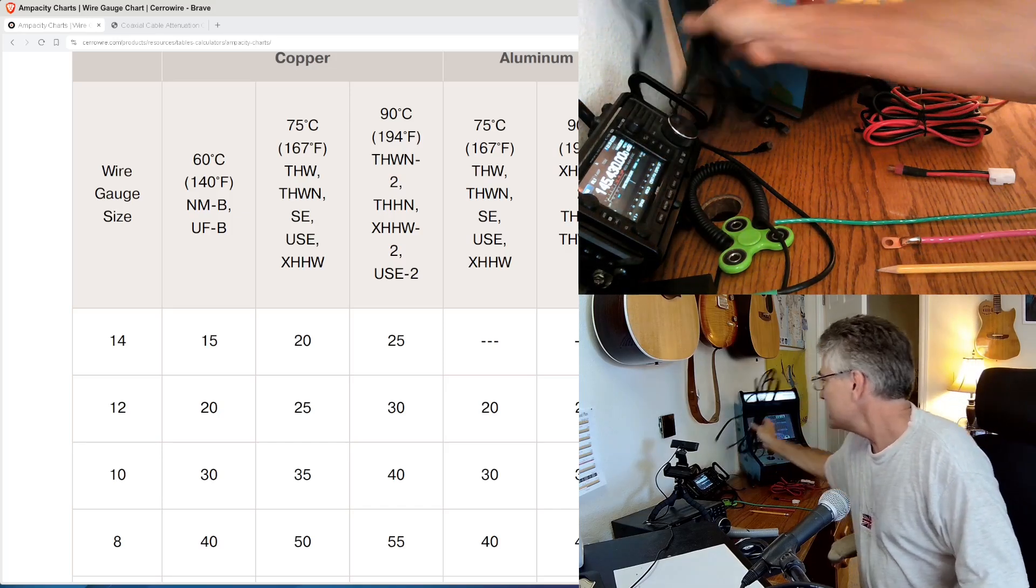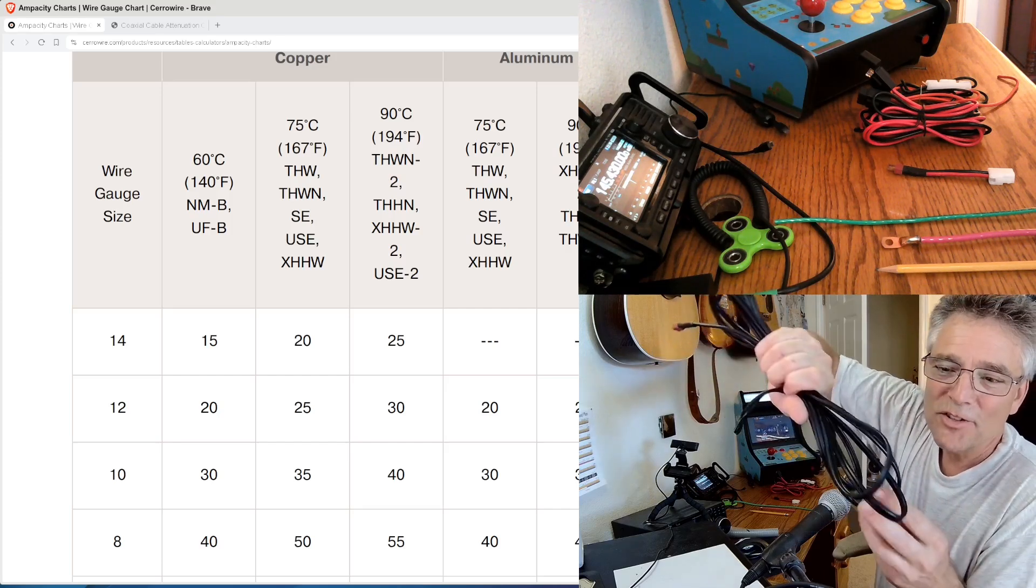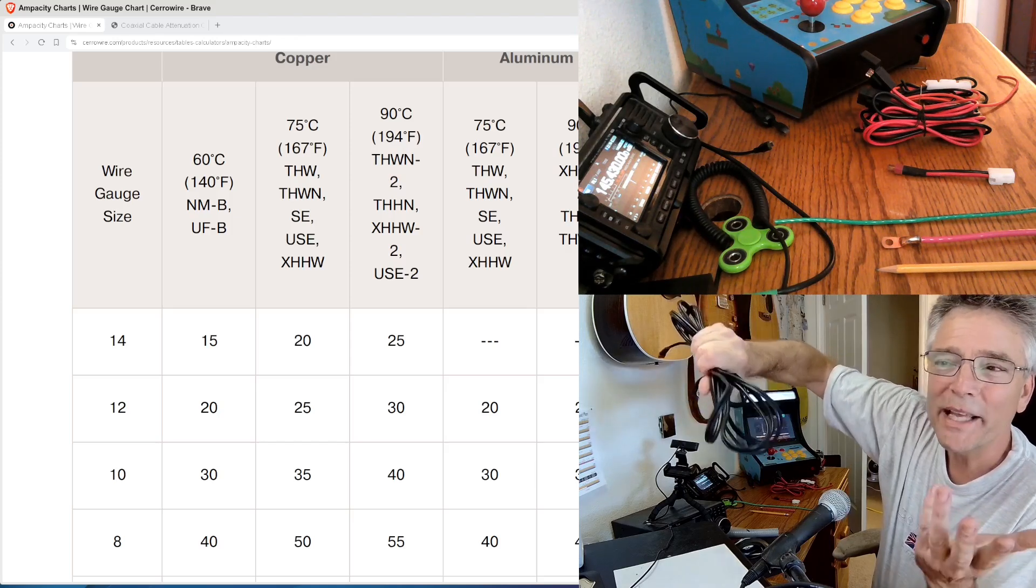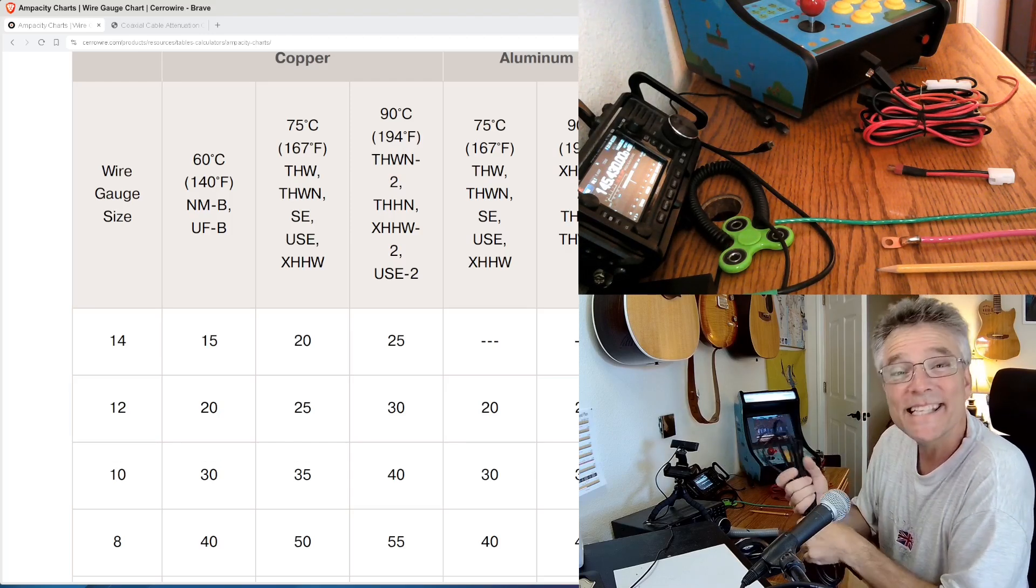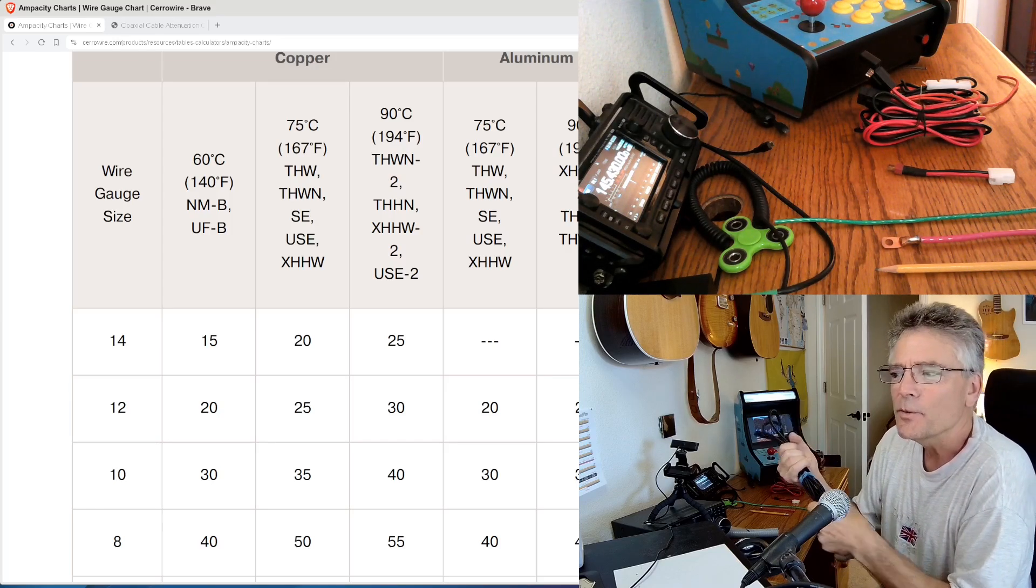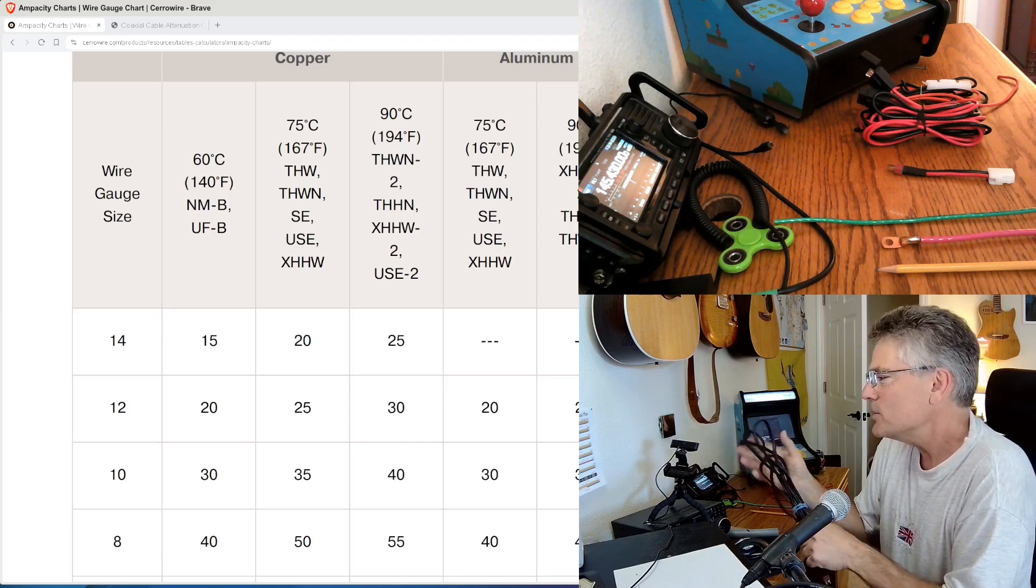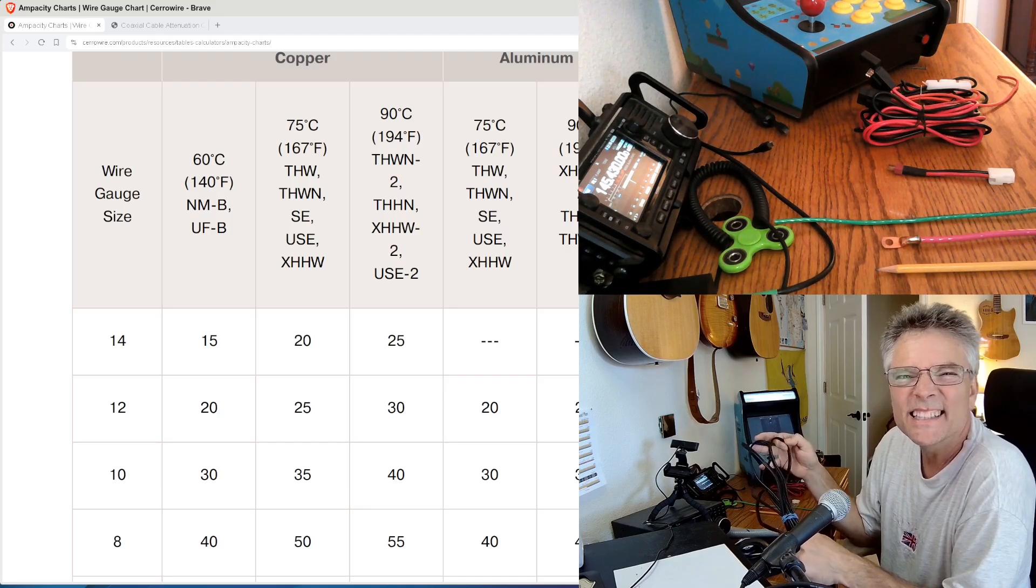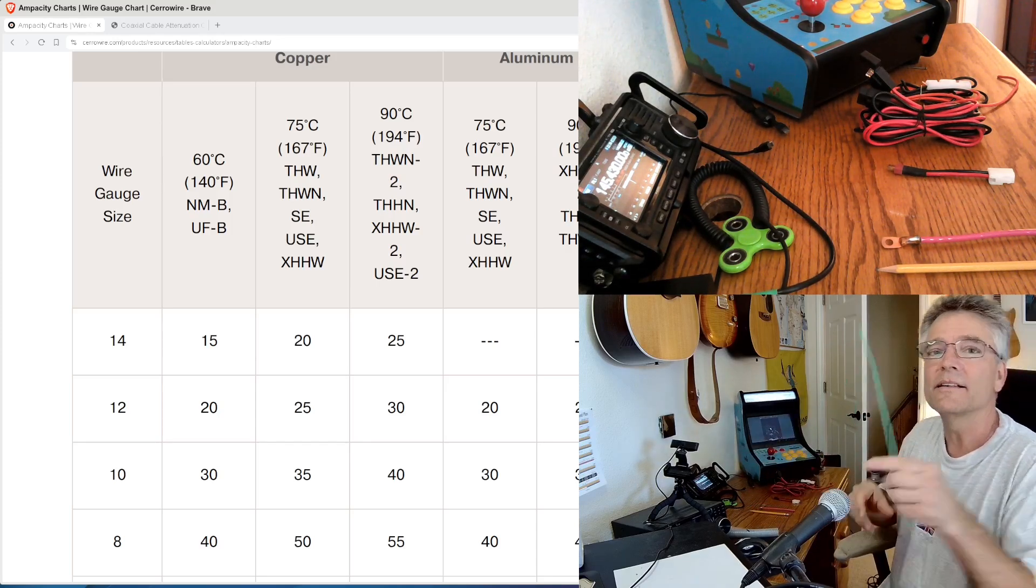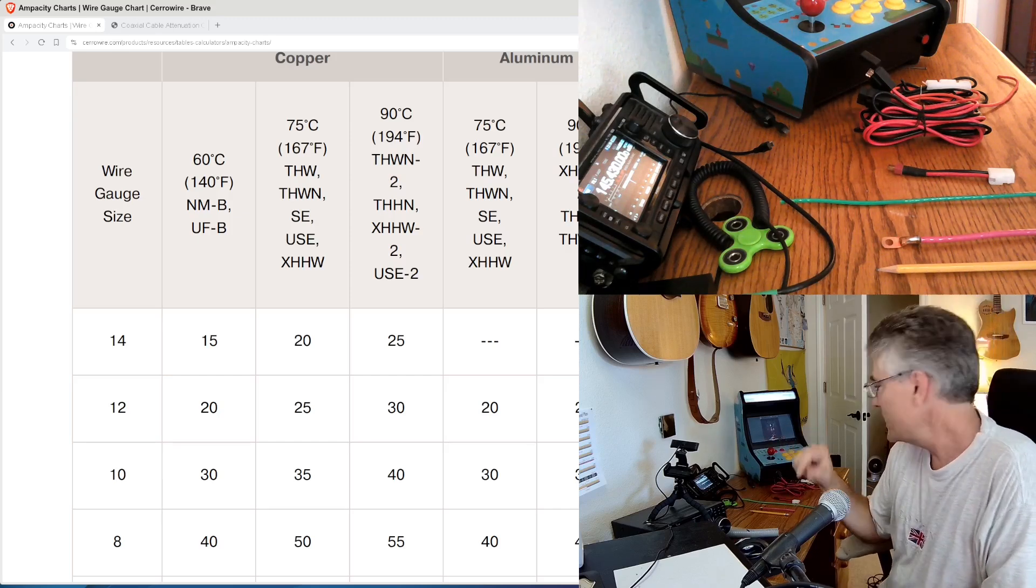If you need to do some longer runs, wire is expensive, let's face it. I actually go to the garden store and get some of this. This is 12-gauge wire and it is direct burial grade, and 12-gauge will carry maybe 20 amps. Now this is not UL listed, so do not put this in your wall, conduit or not. This is ETL listed, which is kind of like a UL listing, it's based out of the UK. But at least here in the Americas, you need to be using UL listed wiring, especially running any kind of current. It's mostly because 12-gauge is 12-gauge, stranded wire, but it's the heat rating on this. Whereas this THHN wire, this UL listed stuff, this is rated at 90 degrees centigrade. This stuff is good to go.